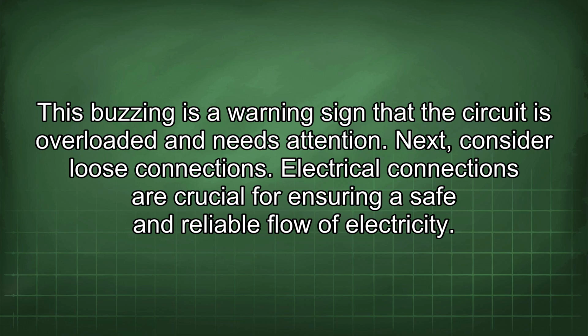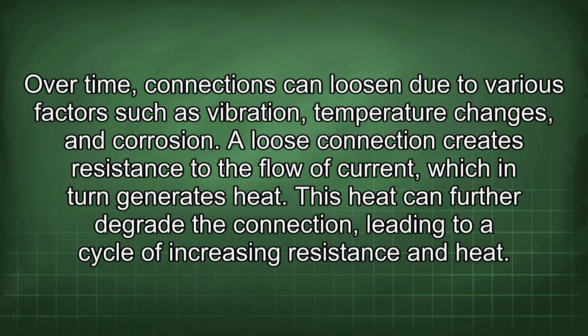Next, consider loose connections. Electrical connections are crucial for ensuring a safe and reliable flow of electricity. Over time, connections can loosen due to various factors such as vibration, temperature changes, and corrosion. A loose connection creates resistance to the flow of current, which in turn generates heat. This heat can further degrade the connection, leading to a cycle of increasing resistance and heat.